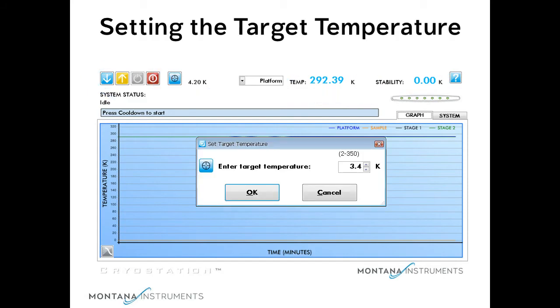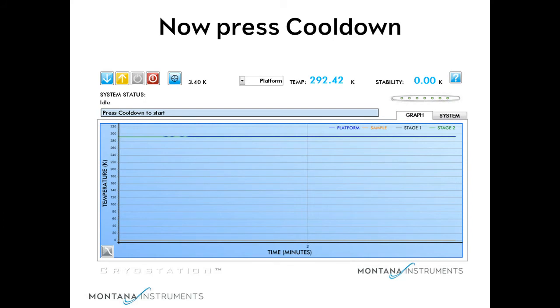The operating range of the system is from 350 to 3 degrees Kelvin. Let's set our target temperature to be 3.4 degrees, for example. Once we set the target temperature, press cool down. It's that simple.